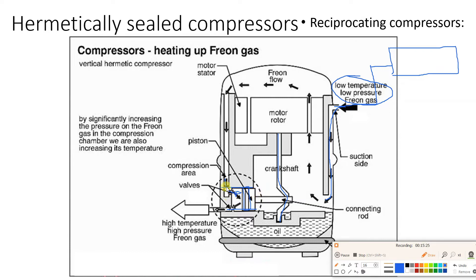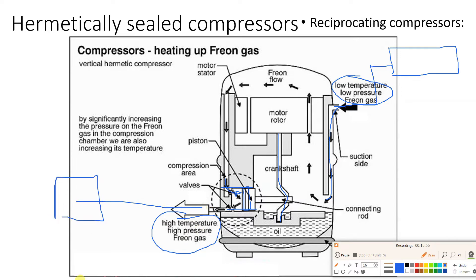During compression: suction is closed, discharge is closed, then whatever refrigerant is trapped inside is compressed between the cylinder valve and the piston. Finally, when the pressure is sufficient, the discharge valve opens and high pressure, high temperature refrigerant gas is discharged. This gas then goes to the condenser. So the refrigerant cools the oil, keeps the motor cool, and also keeps the compressor temperature maintained.